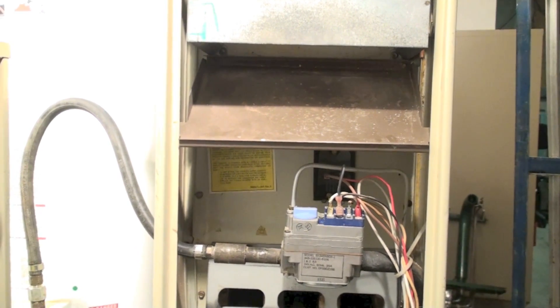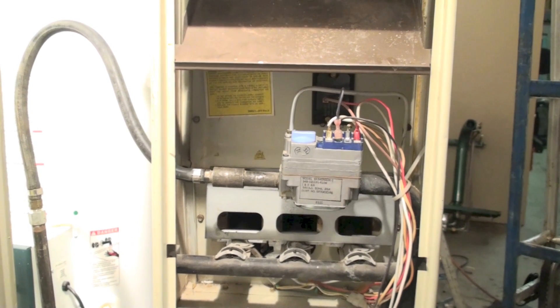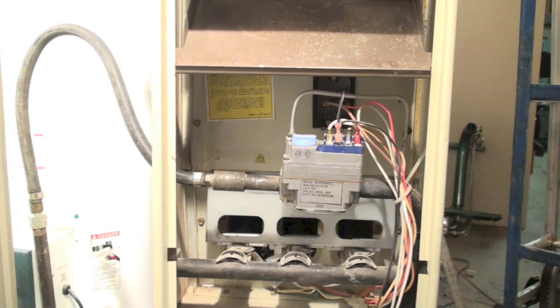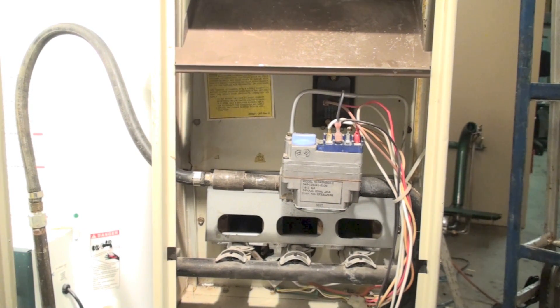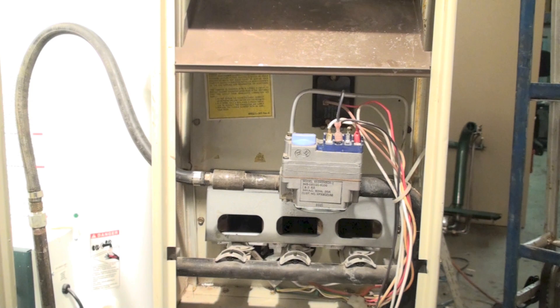There were startup and shutdown inefficiencies with these things. The burners light, they warm up the heat exchanger, fan comes on, blows air across the heat exchanger, burner goes off, it shuts down. There's some inefficiencies on that startup and shutdown, and those were not included in that rating of 80%.